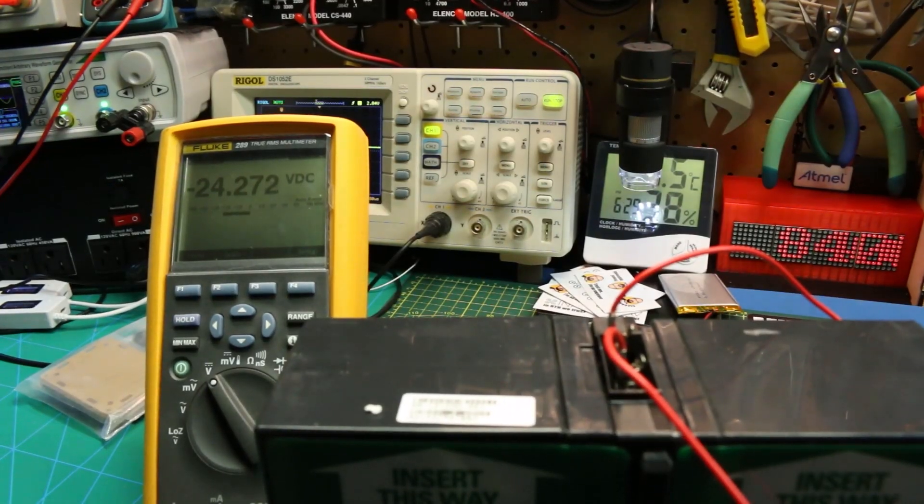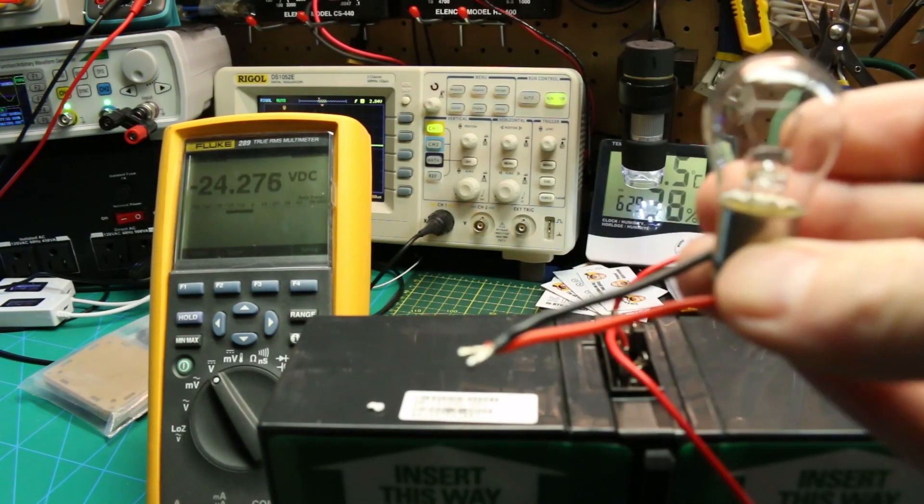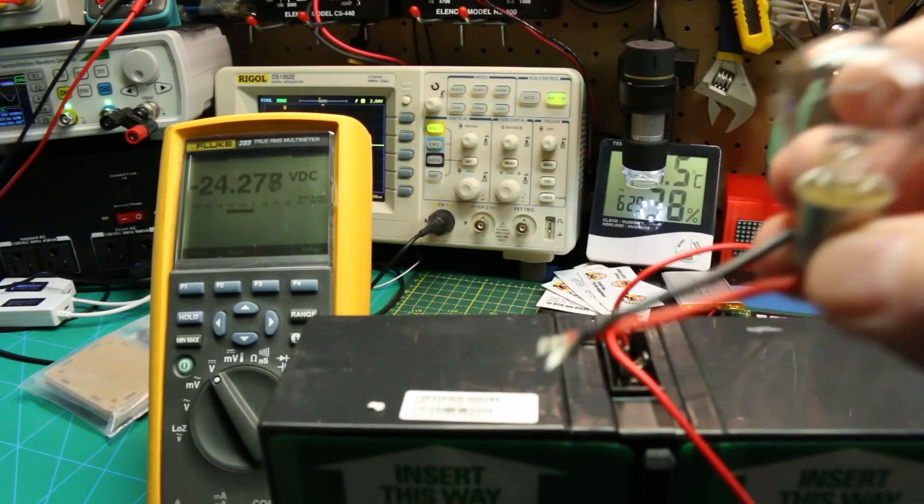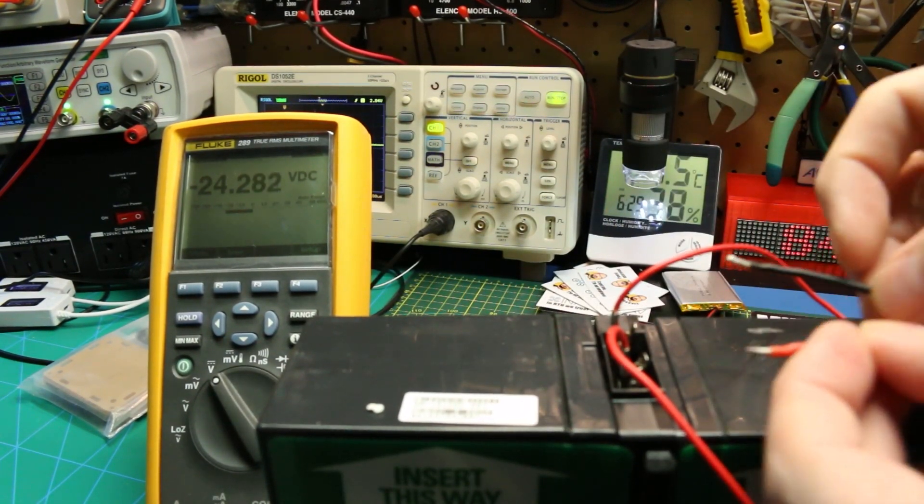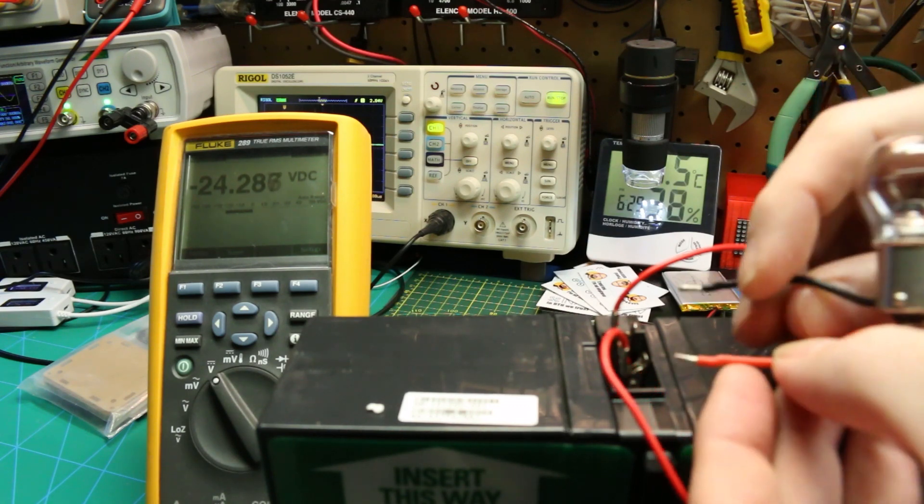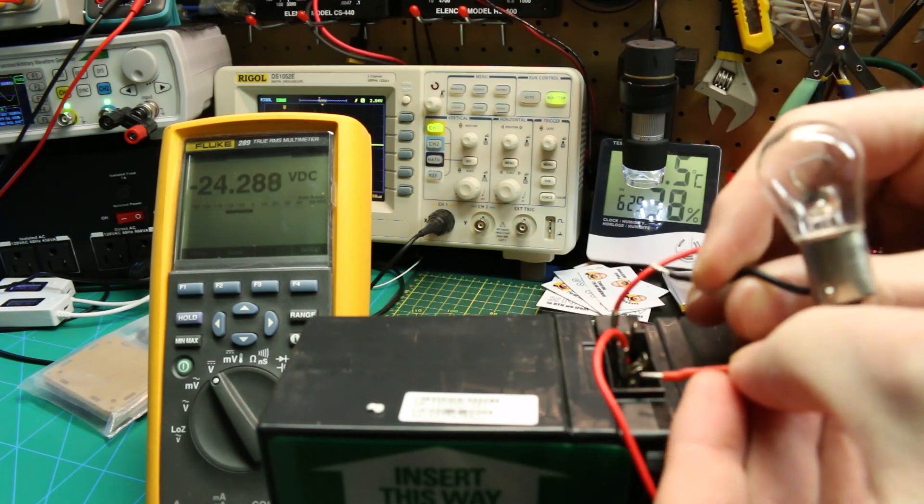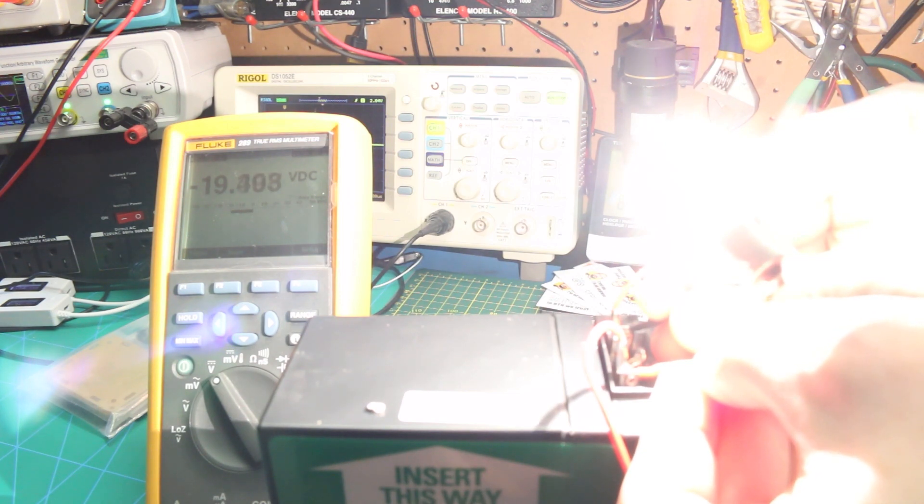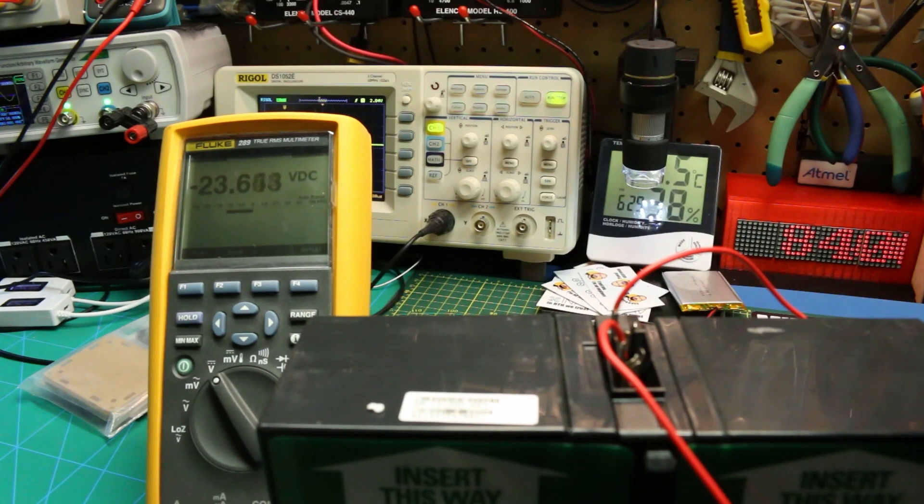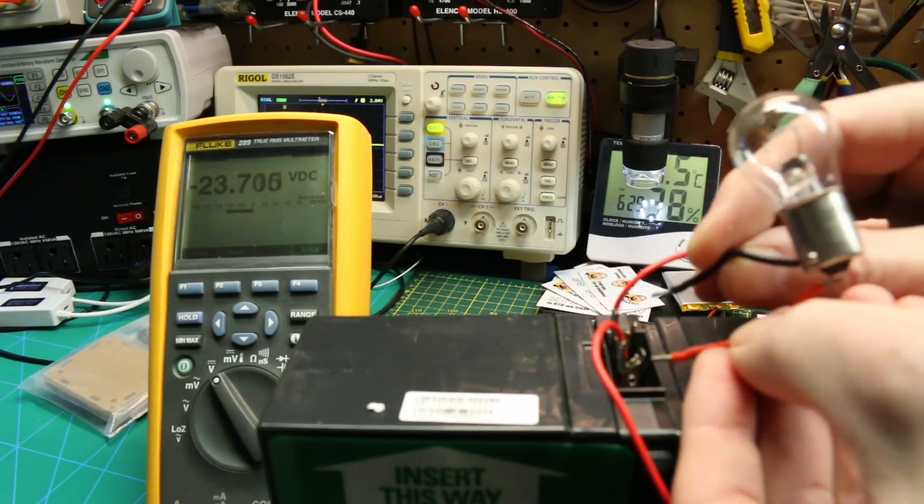With the meter hooked up in parallel at the same time, check out the voltage value. We're already down to 19 volts right away. This is what the UPS is getting angry about. As soon as there's any load, the surface charge on the batteries is just kaput. So quite simple to fix this.